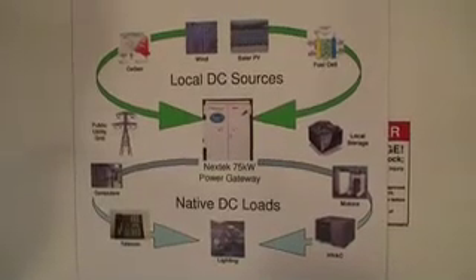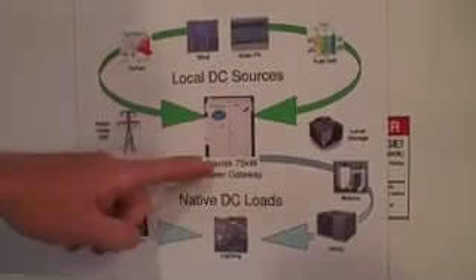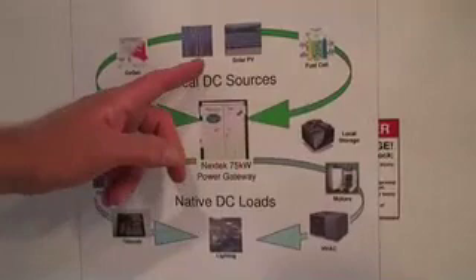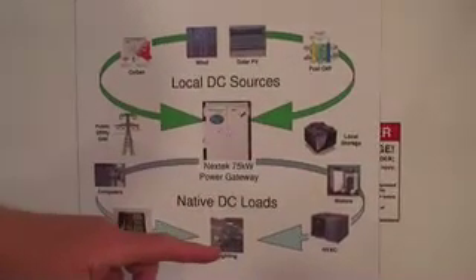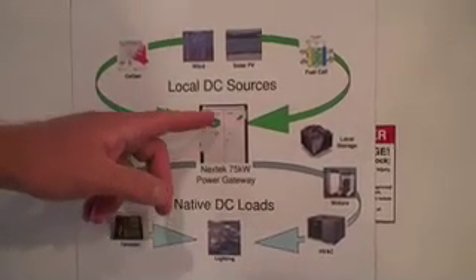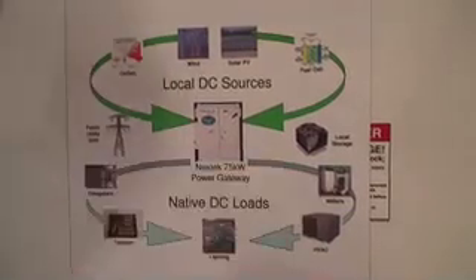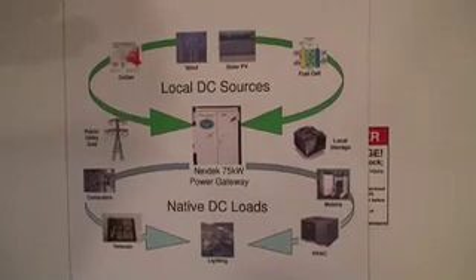The Nextek system in this demonstration is used as a rectifier only, but it's also optimized as a power gateway to integrate different power sources — such as fuel cells, renewables like wind and solar, and co-generation systems. Energy storage can also be placed on the bus. It integrates all of these to supply DC loads including computers, telecom, lighting, HVAC, and motors using adjustable speed drives, where you can feed DC power directly onto the DC bus of the drive.